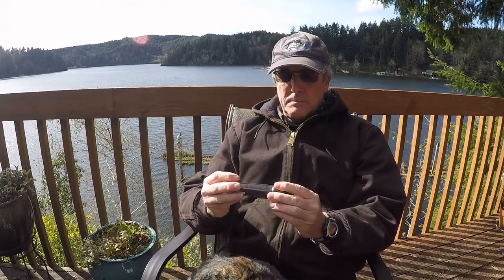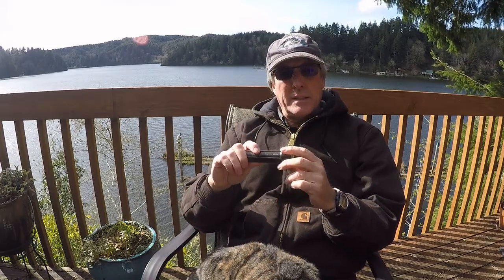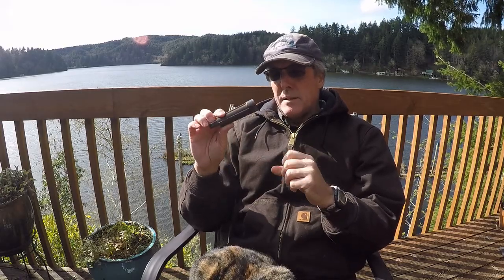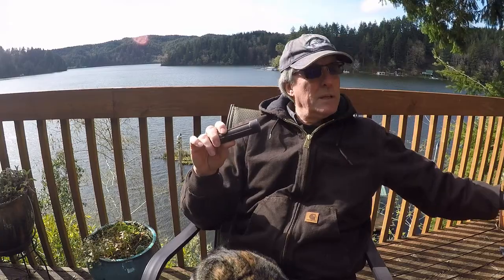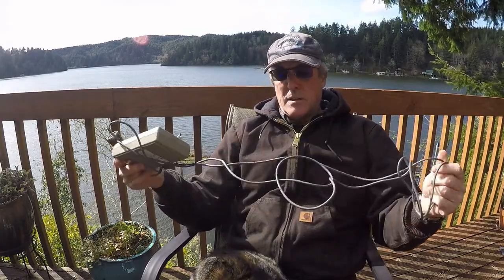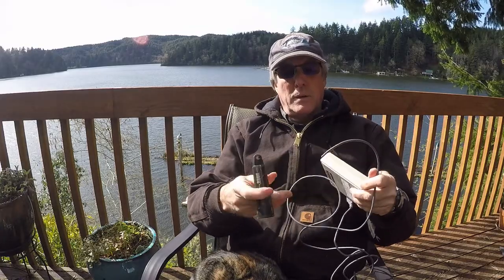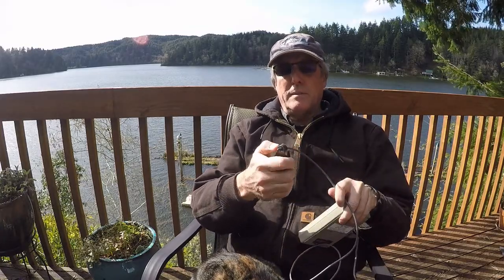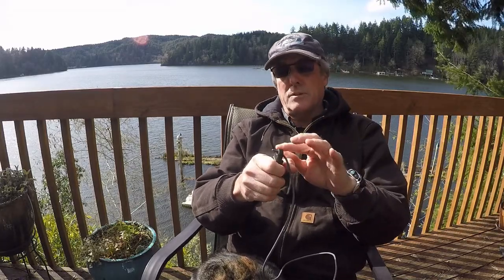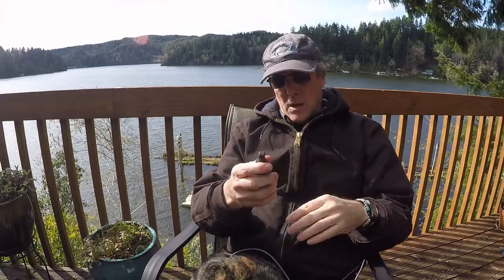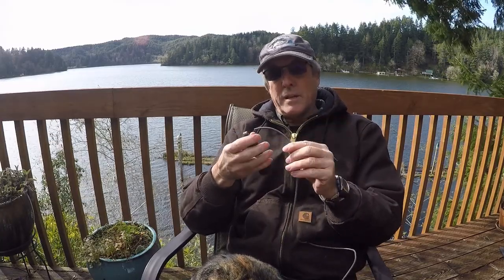Okay, so the first thing we need to do is to calibrate this. This is done by putting the probe and our NIST thermometer, which has this long cable, and generally what we'll do is kind of put this through the hole, because we know that the probe's temperature sensor is right here in this curve. So we will put these into water baths and check to see if the probe is reading the same thing as our NIST thermometer.